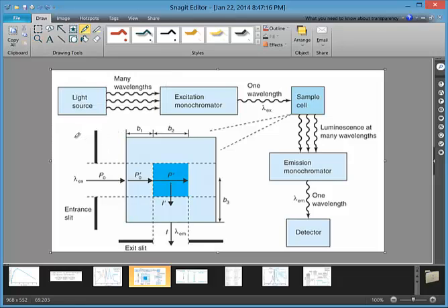In a UV-Vis spectrometer, you typically have a light source, and it's typically white light or something that has all the wavelengths. Those wavelengths are then split, separated, just like think about a raindrop splits the white light from the sun into a rainbow of colors: red, orange, yellow, green, blue. And we call that a monochromator. So out of the monochromator we get just a single wavelength.